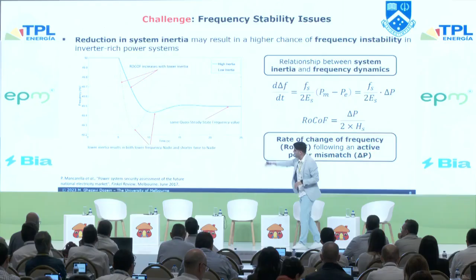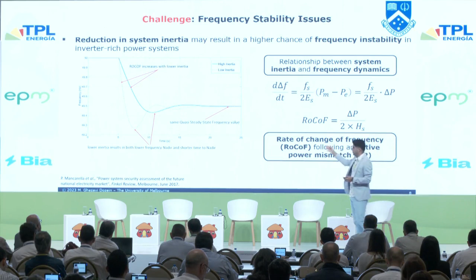When you lose kinetic energy from synchronous machines following a contingency, you get a very high rate of change of frequency, and this increases as you add more renewables. This comes from the classical swing equation in traditional power system dynamics and analysis: any mismatch between active power generation and consumption creates frequency variation, and this variation is higher under low inertia conditions. So there's a higher chance of frequency instability in a renewable-rich power system.